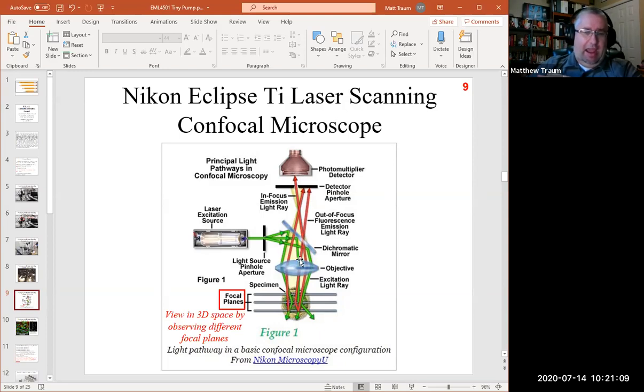And by changing the optics, what you can do is bring different slices into focus and therefore reconstruct a three-dimensional image, right? So these focal planes are all in the Z direction. And so you just change the optics to adjust the focus in Z, and you'll be taking different slices of the sample. All of the rays of light that are not in focus just hit against the aperture wall here and don't go through, and the one that is in focus is the one that passes through and gets detected by the photomultiplier.